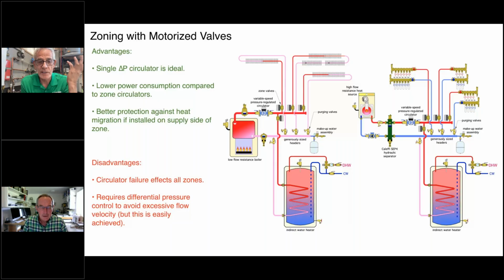Well, the way I look at it, if you've got 8 gallons a minute going into the loop, 8 gallons a minute's coming out the other end, and it's still closing against that volume of flow of water coming through there. They say, well, the pump's added the delta P to it. And so at the beginning, you've got the delta P added to it that the zone valve sees when it's on the supply, where that gets used up or worn away as it goes through there. But again, you're just trying to close the door against that GPM flow that's the same. That's right. The GPM didn't go away at the end.